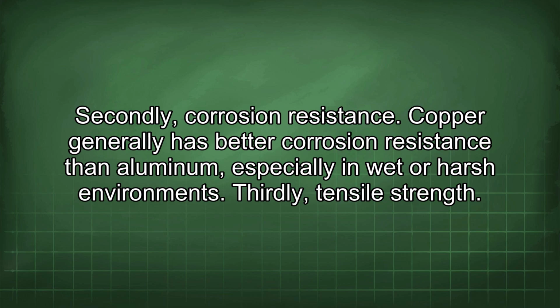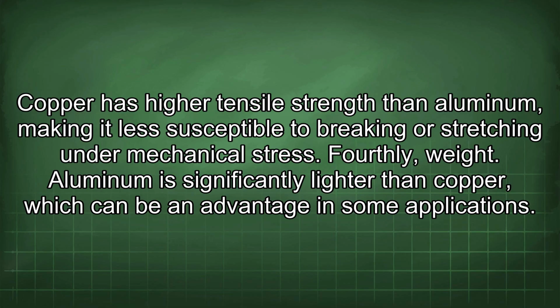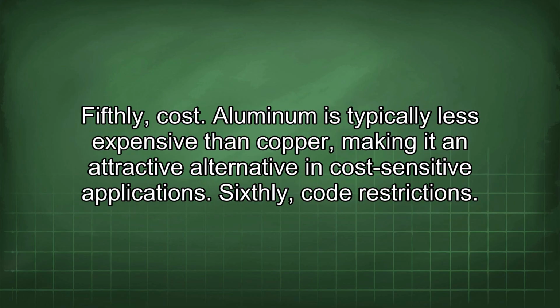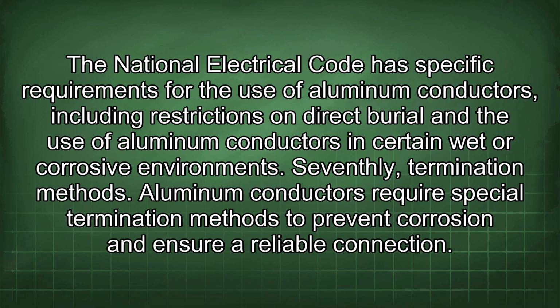Thirdly, tensile strength. Copper has higher tensile strength than aluminum, making it less susceptible to breaking or stretching under mechanical stress. Fourthly, weight. Aluminum is significantly lighter than copper, which can be an advantage in some applications. Fifthly, cost. Aluminum is typically less expensive than copper, making it an attractive alternative in cost-sensitive applications. Sixthly, code restrictions. The National Electrical Code has specific requirements for the use of aluminum conductors, including restrictions on direct burial and the use of aluminum conductors in certain wet or corrosive environments.